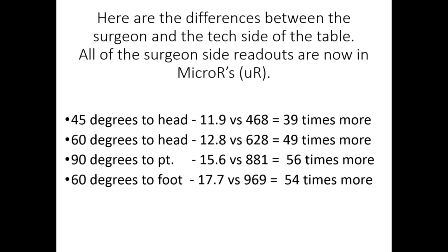Here are the differences between the surgeon and tech side of the table — all surgeon side readouts are now converted to micro R. At 45 degrees to the head: tech side 11.9, surgeon side 468 — surgeon side is getting 39 times more radiation. At 60 degrees to the head: tech side 12.8, surgeon side 628 — surgeon side getting 49 times more radiation. At 90 degrees to the patient: tech side 15.6, surgeon side 881 — surgeon side getting 56 times more radiation.